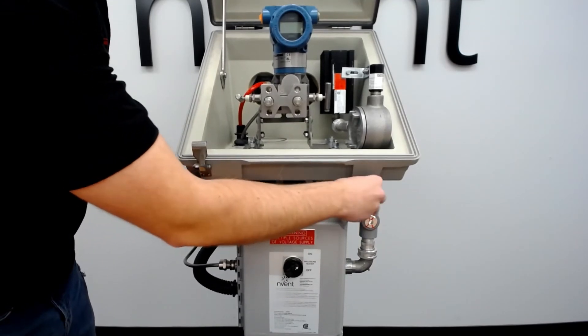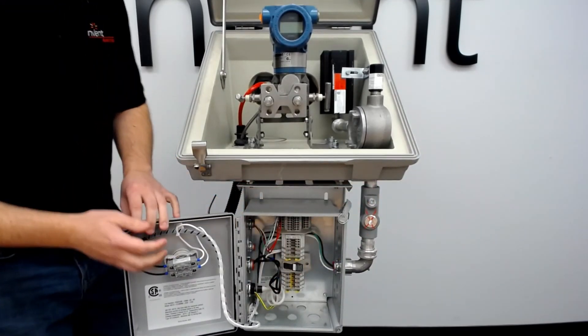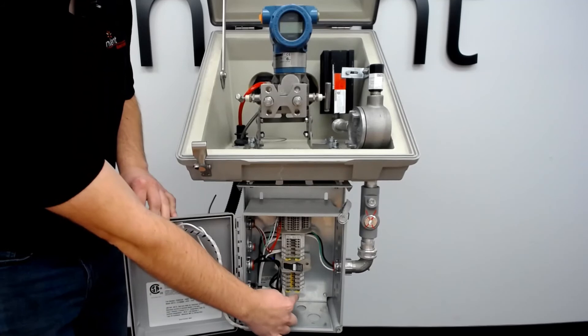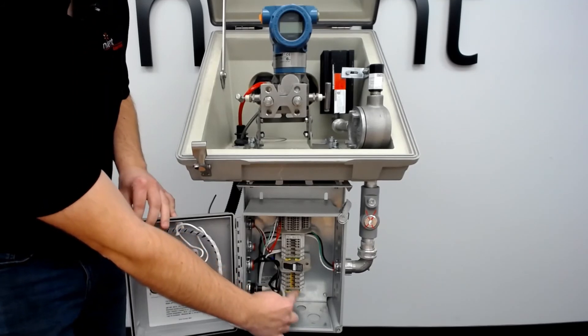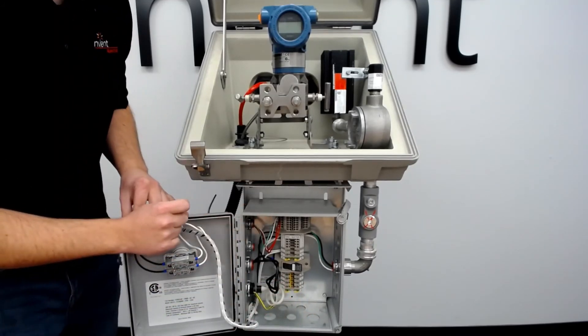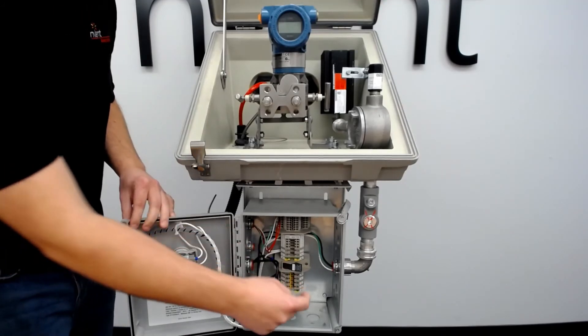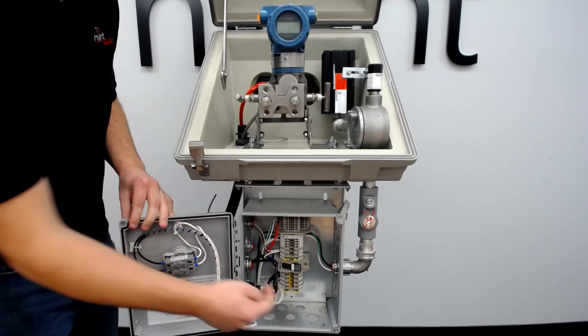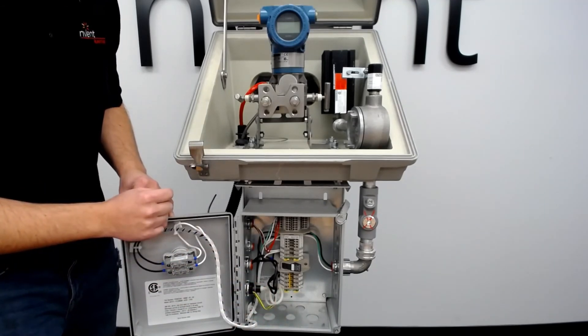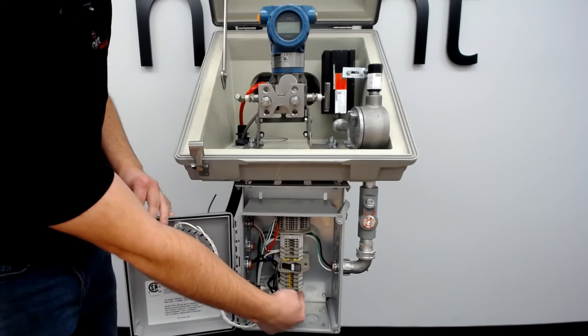Looking inside this junction box, you can see we have terminations for your electric heat trace that are feed-through. Make sure with self-regulating, it does come with the ground, whereas mineral insulated does not, and that you account for the right number of ground terminations inside those heat trace terminations.